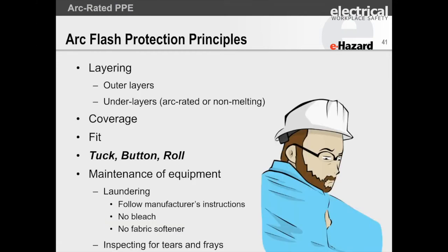Arc flash protection principles: the outer layers need to be arc-rated, and the underlayers need to be arc-rated or non-melting. You don't have to have the outer layer at 20 cals. You can use 2 layers, and if they're arc tested together, you can use those to develop that protection.